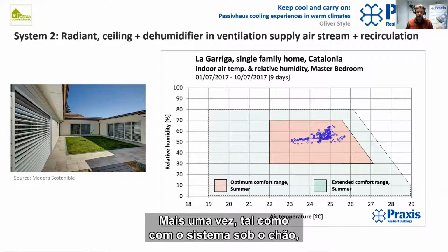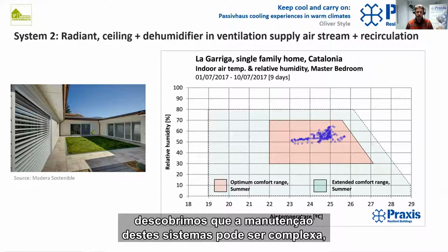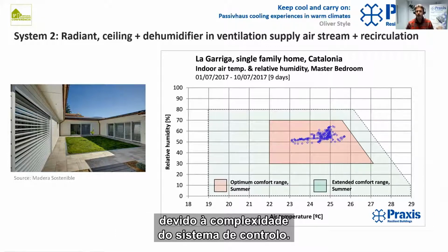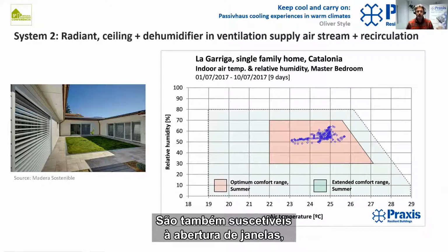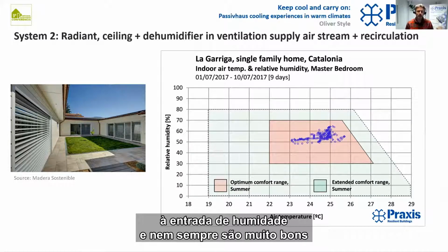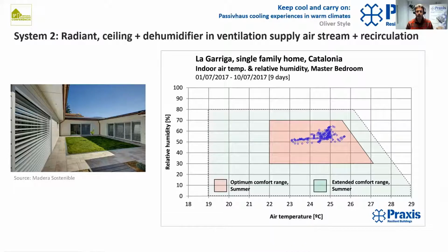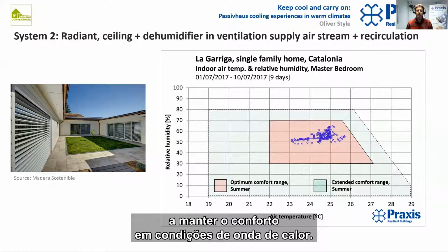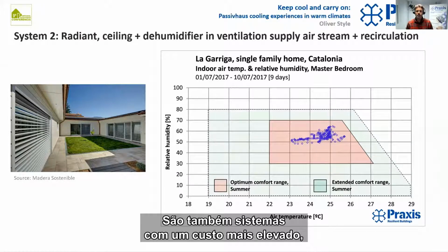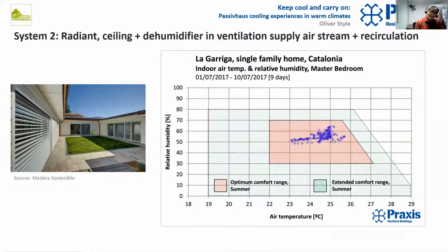Again, as with the underfloor system, we found that these are systems that can be complex to maintain, basically due to complexities in the control system. They're also more susceptible, of course, to windows being open, humidity coming in, and not always that good at maintaining comfort during heat wave conditions, and also systems that have a higher cost. These are not the cheapest.